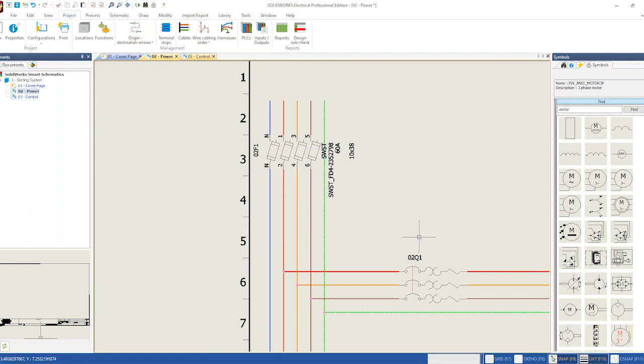One thing about this is my symbols have default attributes applied that get pulled from the manufacturer's parts library. The terminal designators are defined there, and it brought in the manufacturer, part number, amp rating, and the size of the fuse needed.